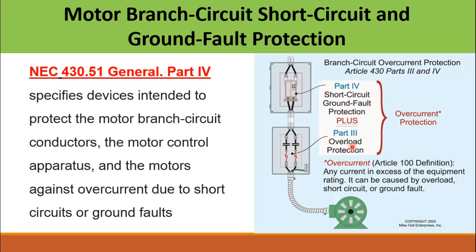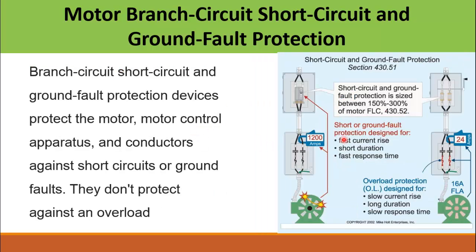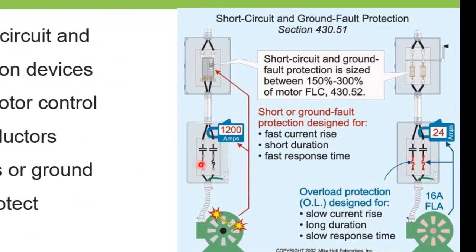In a previous video I also explained how to properly select the overload protection for motors according to the NEC standard. NEC 430.51 general specifies the devices intended to protect the motor branch circuit conductors, the motor control apparatus, and the motor against overcurrent due to short circuit and ground fault. This standard does not cover overload protection, since that is already provided through the overload device installed with the circuit breaker. Unlike motor circuits, in lighting circuits we don't normally install an overload device such as overload relays — the circuit breaker provides both overload and short circuit protection. But in motor circuits we normally install the circuit breaker and a separate overload device.